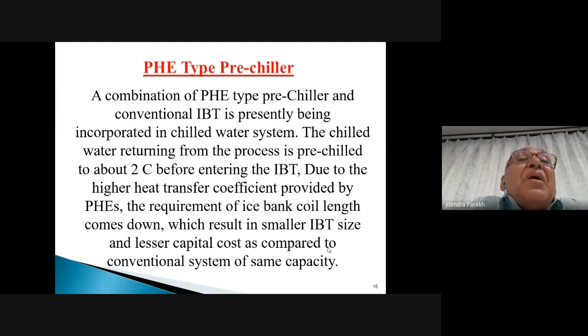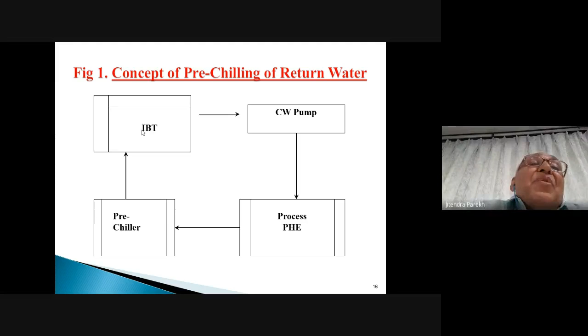Next, please. I have shown the diagram also, where you can see on the left on the top there is the IBT system, then our CW pump is there, then a process PHE. From there it goes directly to the pre-chiller and then to the IBT. So chilled water is cooled down by 2 degrees in the pre-chiller and then goes to the IBT. In that way the size of the IBT can be reduced and efficiency can be increased. Next, please.